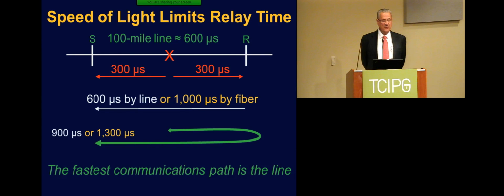So I'm waiting for you to tell me if you saw it in the forward direction, in a directional comparison scheme, and you're waiting for me. So it's 300 microseconds by the time you know it, and if you could tell me through free space or on the transmission line itself, it would be the line length, 600 microseconds, so we're already into it 900 microseconds before I could possibly trip my circuit breaker based on my information and yours. Pretty interesting, huh? You can't beat it.